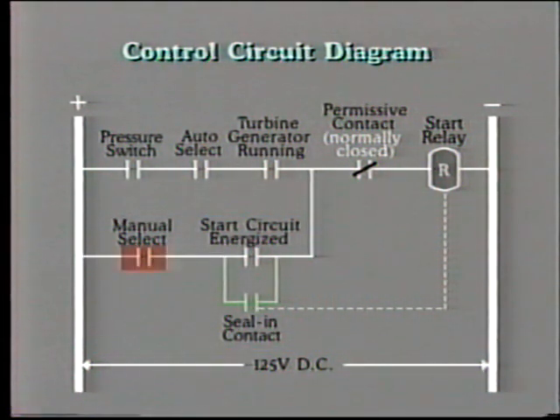To start the pump, the auto manual selector must be in manual, and the start contact must be closed. This would normally be energized by a starting circuit, which would include a seal-in contact arrangement around the starting switch or push button. Once again, the auxiliary pump and motor are protected by the same permissive contact.